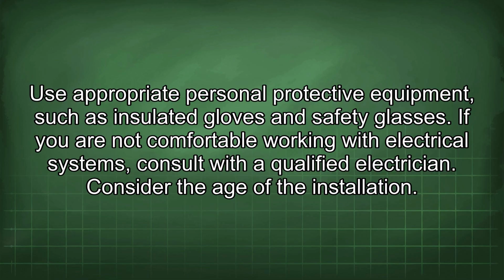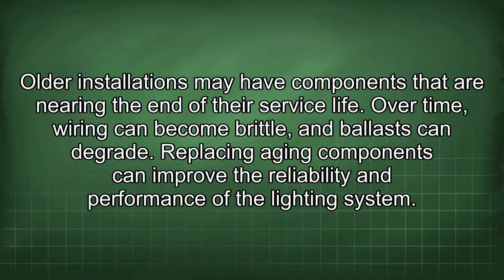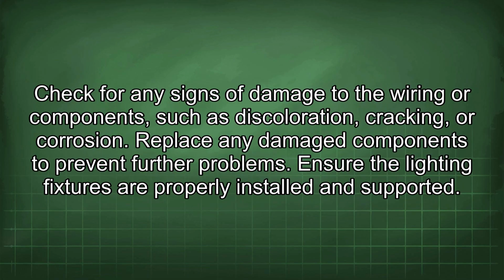Consider the age of the installation. Older installations may have components that are nearing the end of their service life. Over time, wiring can become brittle and ballasts can degrade. Replacing aging components can improve the reliability and performance of the lighting system. Check for any signs of damage to the wiring or components, such as discoloration, cracking, or corrosion. Replace any damaged components to prevent further problems.